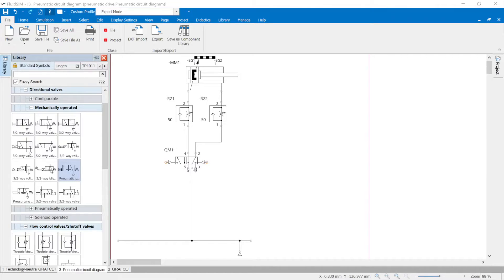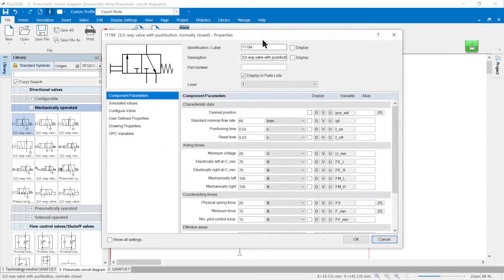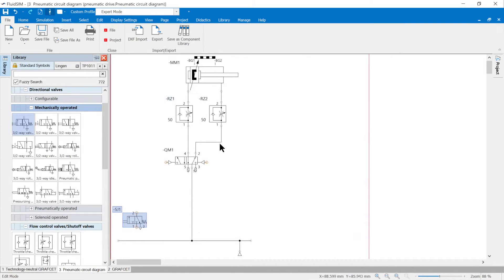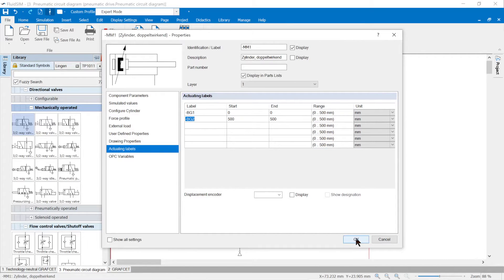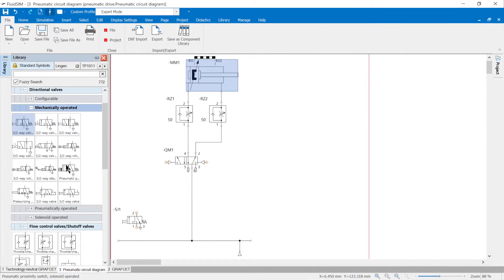To link pneumatic sensors to the drive: for the problem, a pneumatic three/two-way valve normally closed is required. It is used as a start key SJ1. The end positions on the cylinder must be monitored. In the properties of the cylinder, the actuation marks BG1 are entered at 0 mm and BG2 at 500 mm.